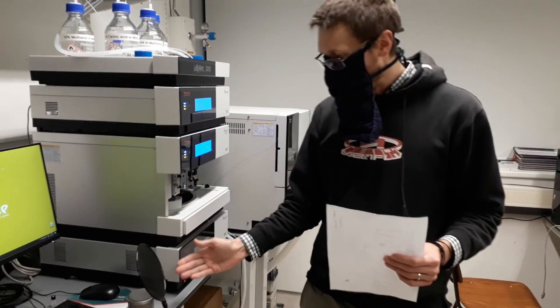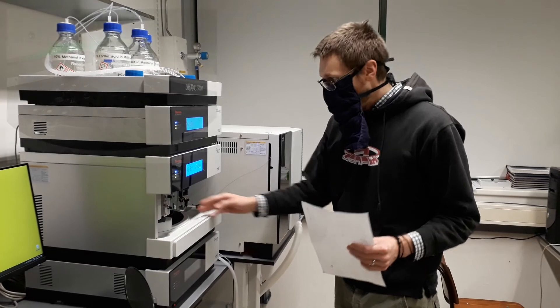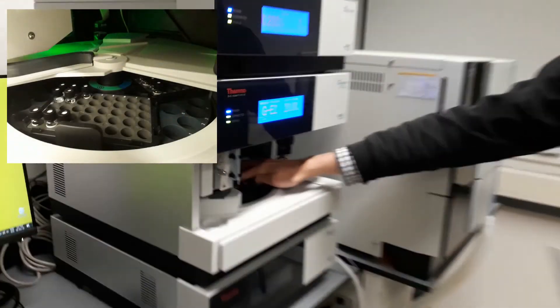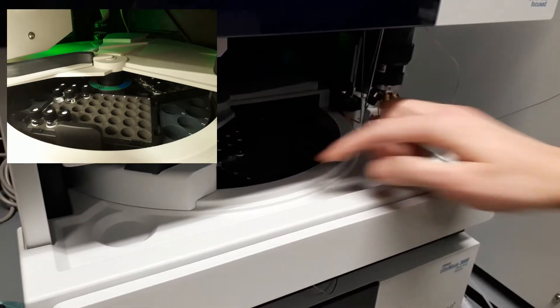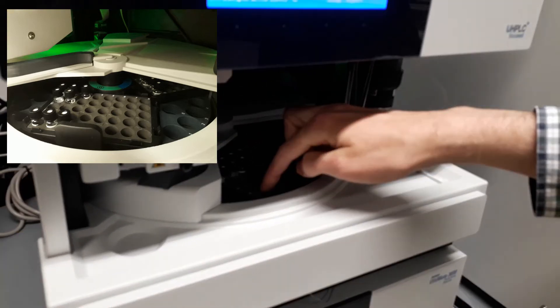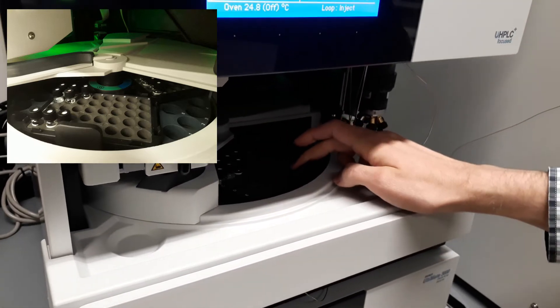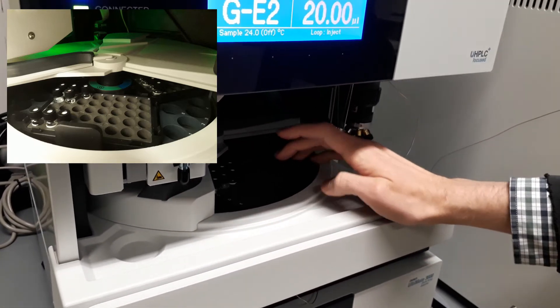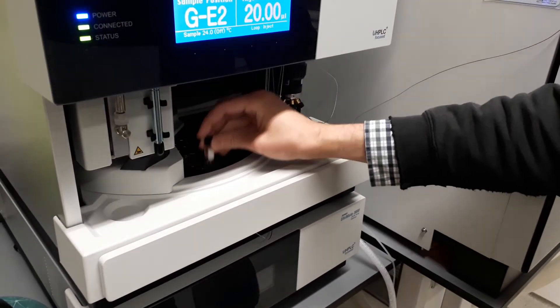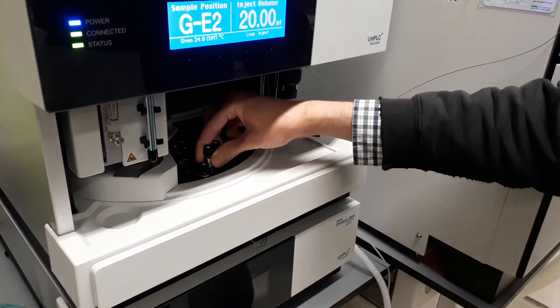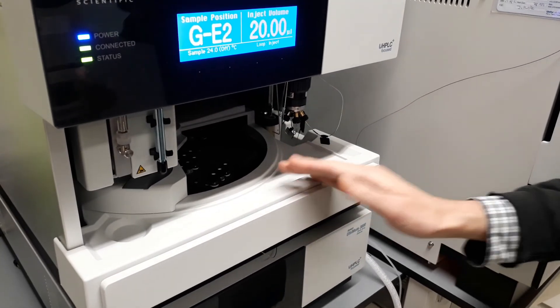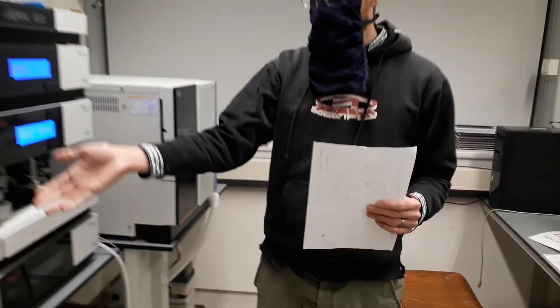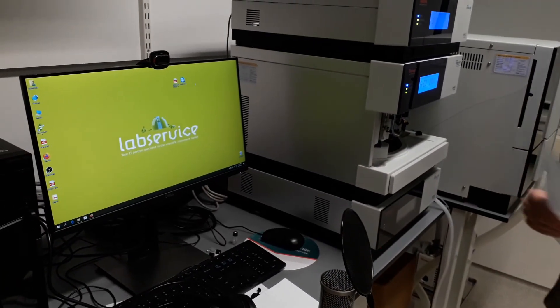So you take your blank and some samples, get to the machine, rotate to the shelf which is green with the G label, and use the E line because that's the line which is predefined. You have quite some vacancies here. For now, submit the normal line, GE1 for the blank, then put your samples after the blank. Now you can step to the PC and continue with the configuration.